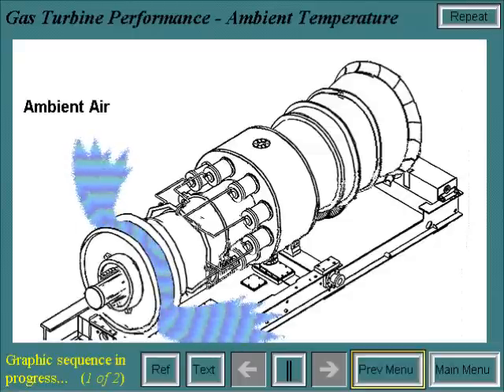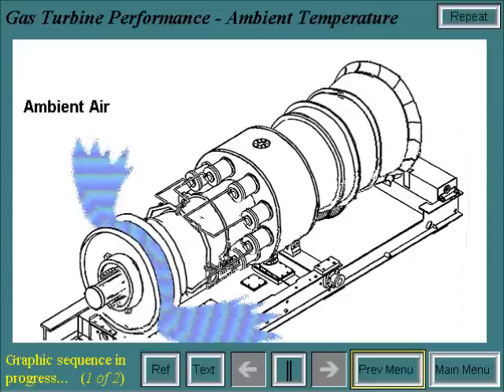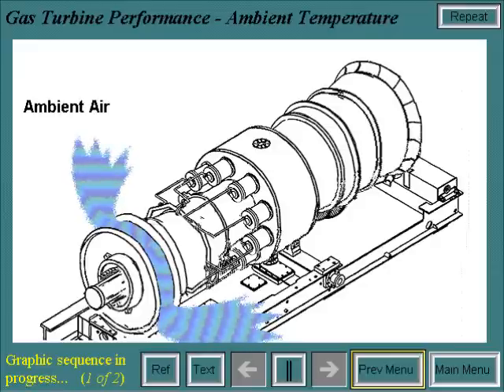Since the gas turbine is an ambient air-breathing machine, its performance will be changed by anything affecting the mass flow of the air intake to the compressor. The most obvious are changes in the reference conditions of 59 degrees Fahrenheit and 14.7 PSIA.